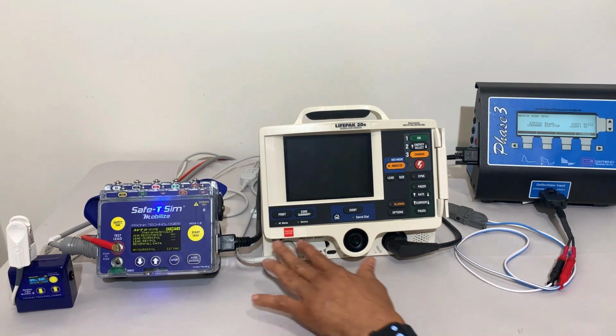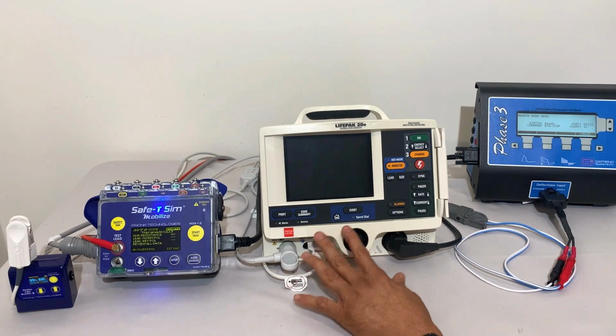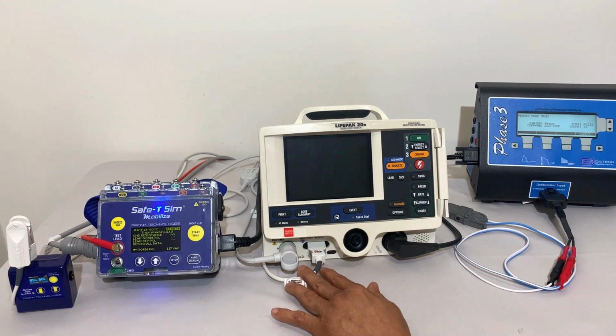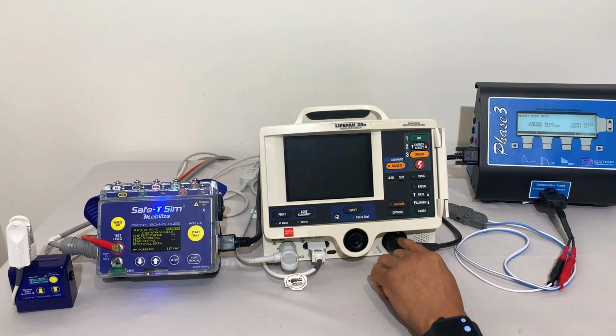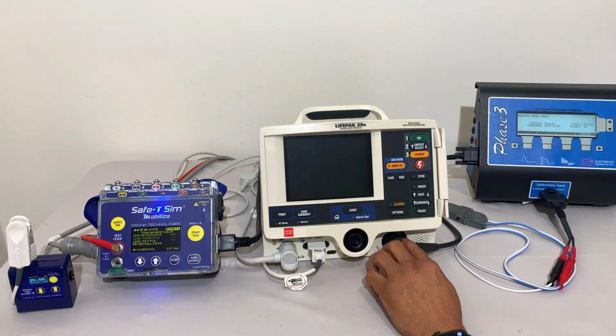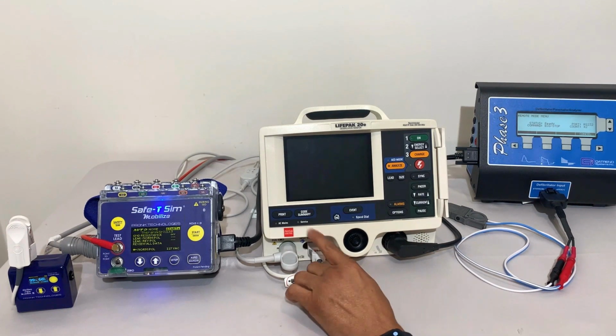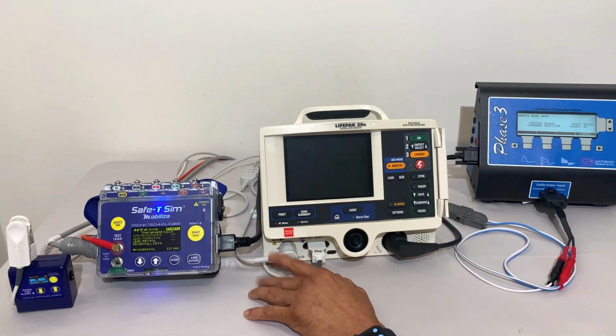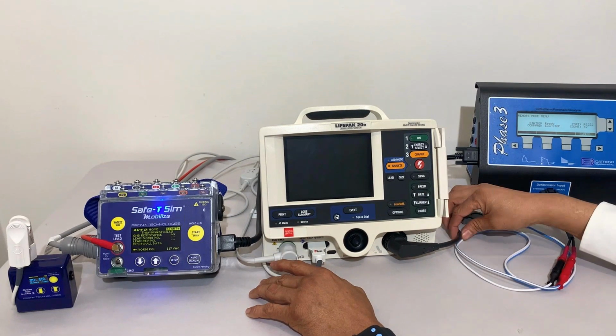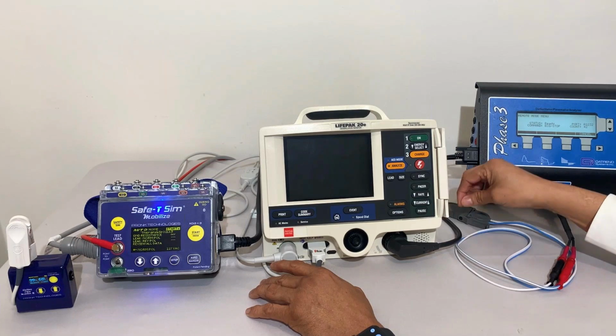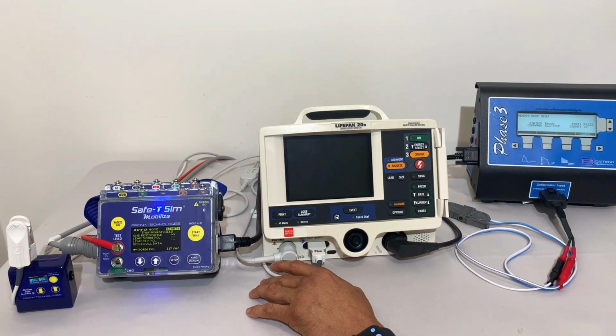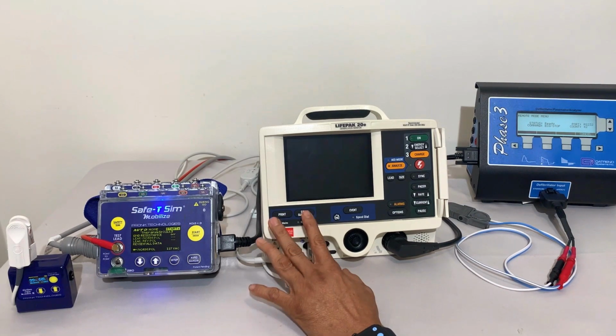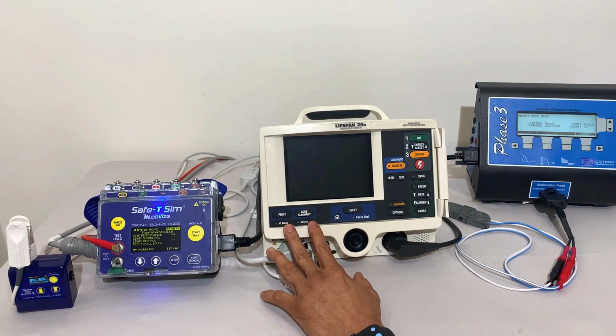And as we're connecting the cabling and the accessories to the defibrillator, we want to make sure we inspect it all, from the power cord to the quick combo cable here. We want to inspect the connectors, both on the defib side and on the cabling side, for all of the cabling, including the SpO2 and the ECG, to make sure we don't have any damage, particularly looking out for any frayed cabling, any exposed wires. We definitely want to make sure we've replaced and taken care of that. So can't emphasize enough the importance of the physical inspection.